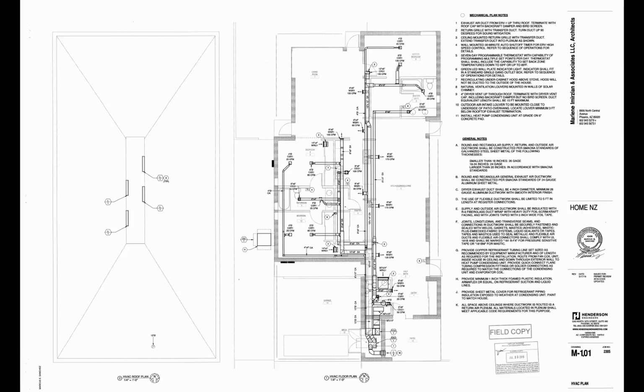It has a very large return here, which is actually, interestingly, doing a similar thing to the hotel units, in that this space right here is a 10-foot ceiling, and this space right here is an 8-foot ceiling, and this, in the bathroom, has a 7-foot ceiling. And so what happens is this very large return air duct comes and sits in this furring wall and returns all of the air from the open spaces. And so you always have to think about the balance of the supply and the return. This is the schedules for all of those different individual units and the registers.